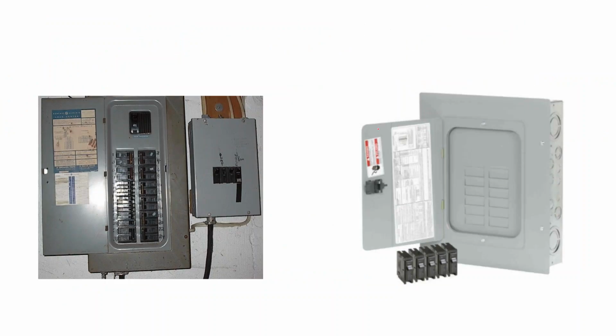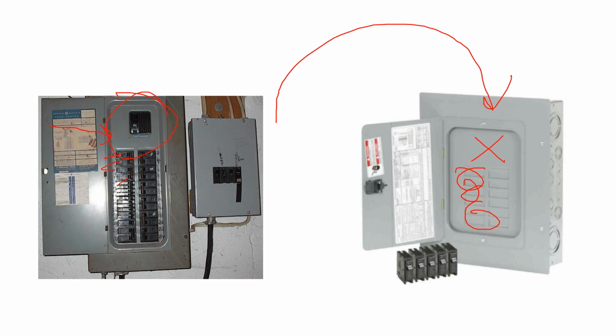And so to kind of visualize what we're talking about here, we're all used to seeing our residential panels with breakers on them and then a main switch. You can also find distribution panels that just have slots for breakers on them, where there is no main switch. And guess what? Those panels are cheaper. So if you can get away with a cheaper panel that just might be a distribution panel for solar, you can do that. You don't need to have a main. It comes down to that 6-handle rule making another appearance.